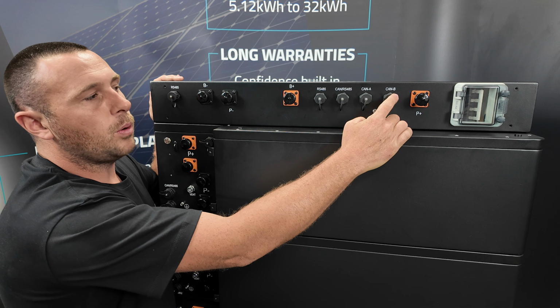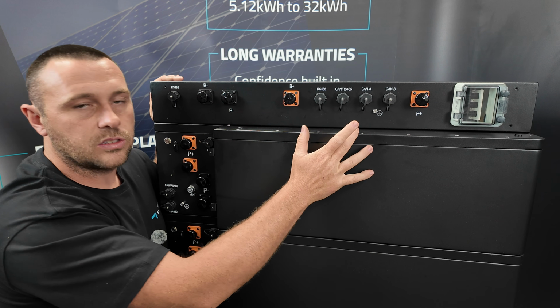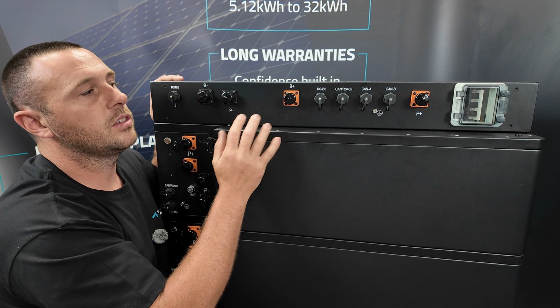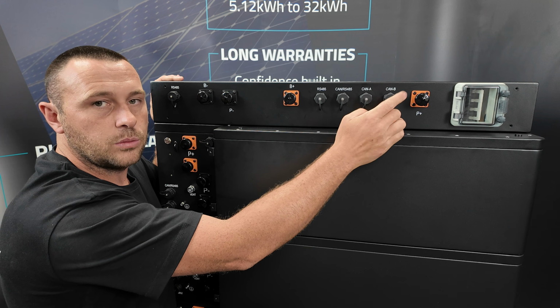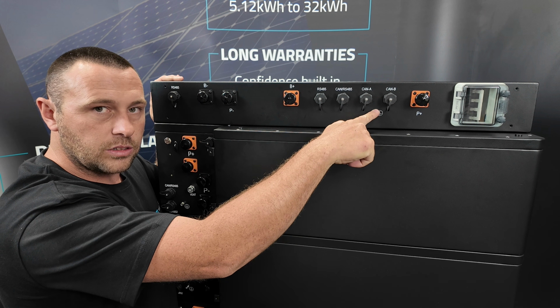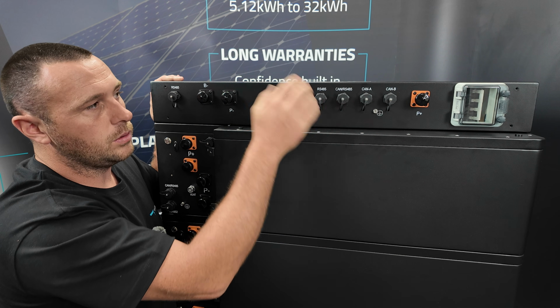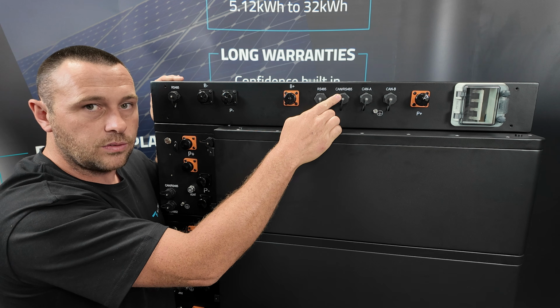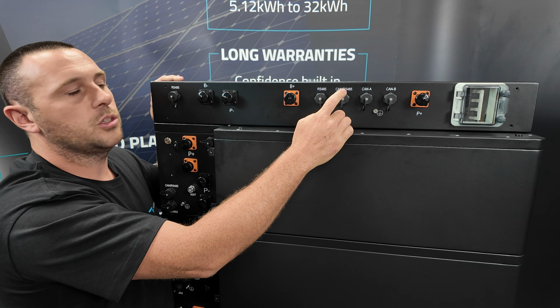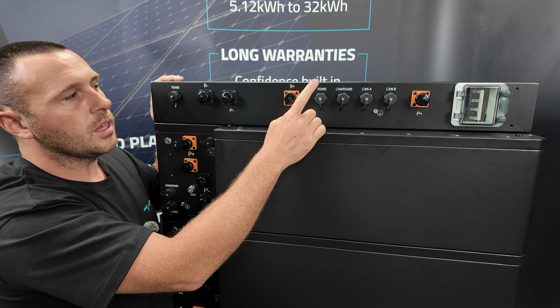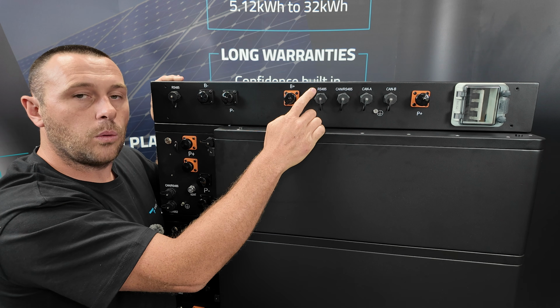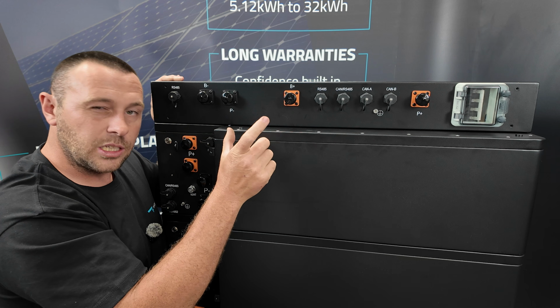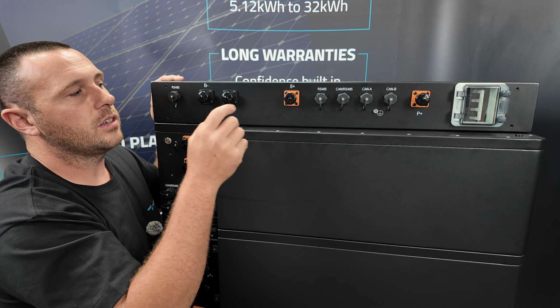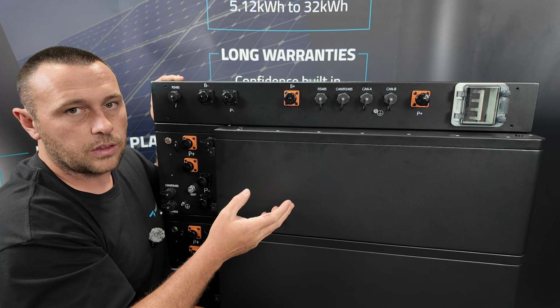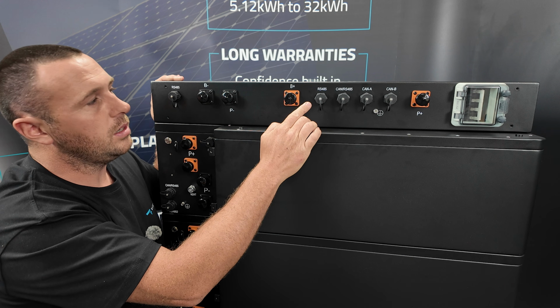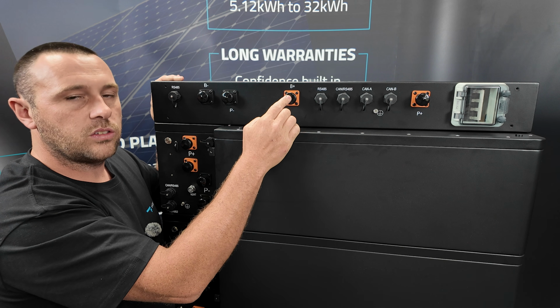CAN A and B port is for parallel battery communication. So if you are running multiple stack batteries, parallel communication will be through these 2 ports here. There is an earth grounding screw for the top control panel. We have a CAN RS485 port. This is for communication with your inverter. This RS485 port is for PC communication, which comes with that USB lead that is in the box. So if there's ever a need for a software update or something like that, you can plug into this with your computer. There is the battery positive lead here.